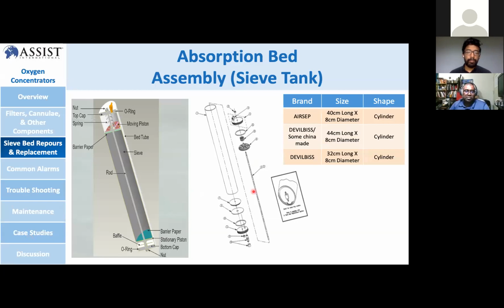So when you're going to do a zeolite exchange, you need to know what components you have inside this particular zeolite tank. There's a spring, a nut and the O-ring. These are the O-rings that are always going to leak. Sometimes, due to vibration, you get O-ring leaks. So eventually humidity goes in and makes the zeolite very hard. There's a moving piston, and you have a baffle. On both sides, you have an O-ring. These O-rings are very important to avoid any leaking. So remember that.